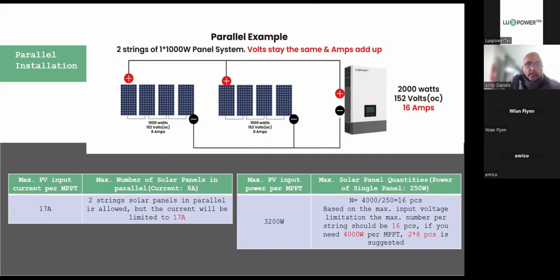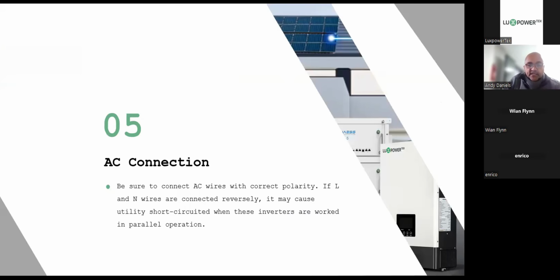Okay. Right, so let's go to the AC connection. On the AC connection, make sure that the AC polarity wires are correct. Okay, so we do have protection for reverse connection, but obviously you've got to be sure that you get this right, because on your connection you're going to be using a neutral bar, so you can't put a live on there. It'll be quite a nasty little short circuit, and a mistake that you only do once.